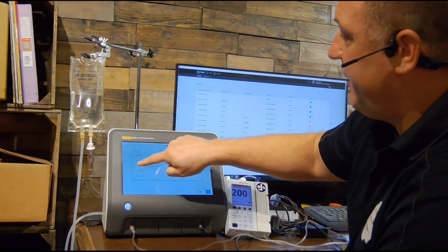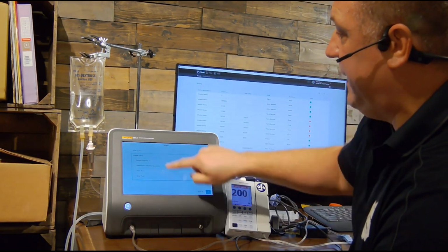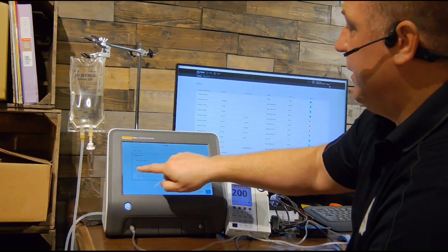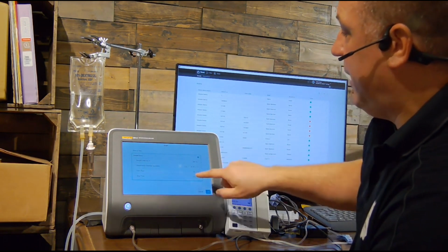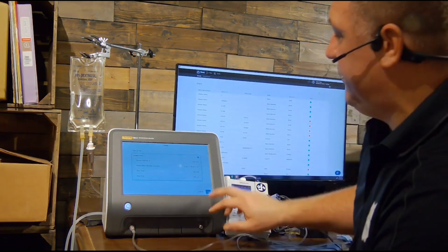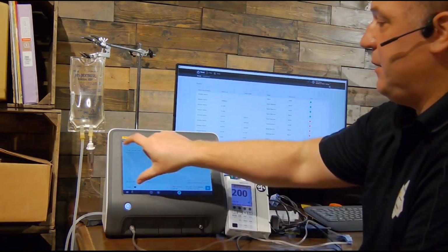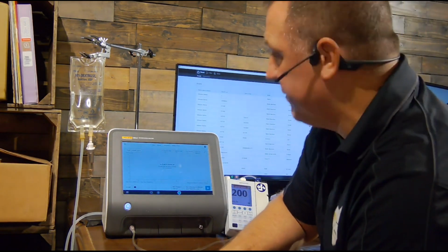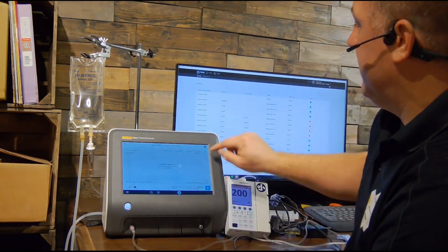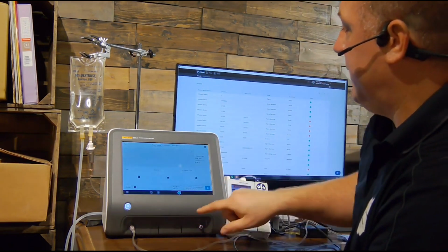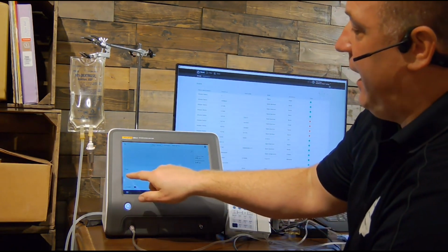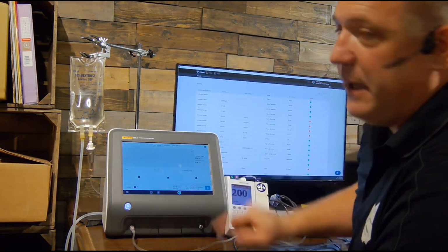And anything that has a red star, you have to program that in. So your sample interval, your observation window, your start time, stop time, your delta, all that gets programmed into it. Once you program that in, you'll then be able to graph your trumpet curve across the screen. Make that small again, and you have your time, your volume, and your mean flow.